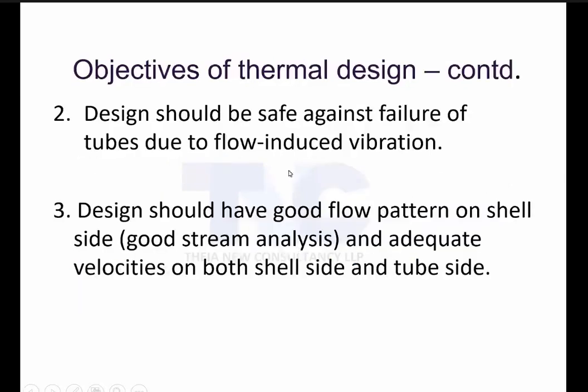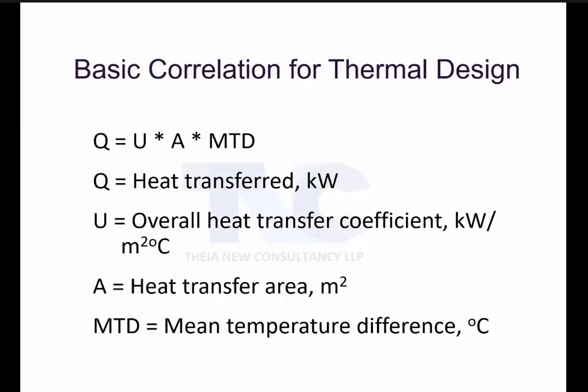As I said, the design should be safe against failure due to tube flow-induced vibration. This is mandatory, no trade-off. The design should have a good flow pattern in the shell and stream analysis, and adequate velocities in both the shell and tube. You need adequate velocities to have a proper heat transfer coefficient.